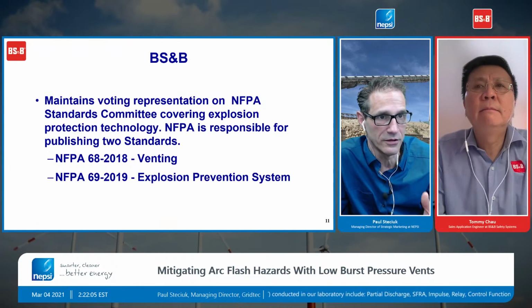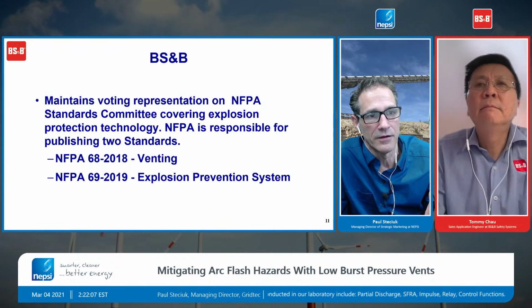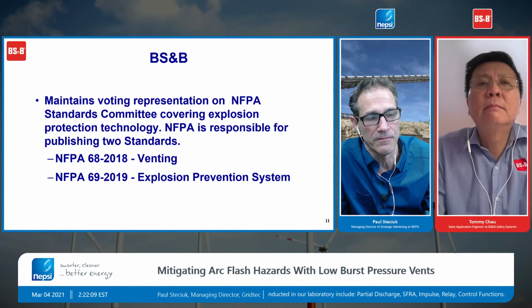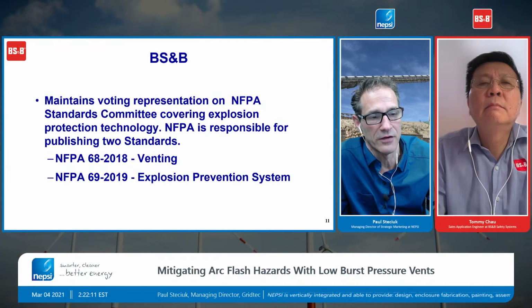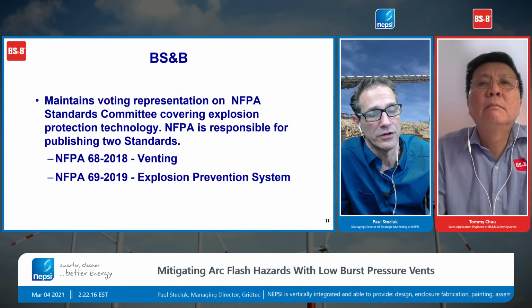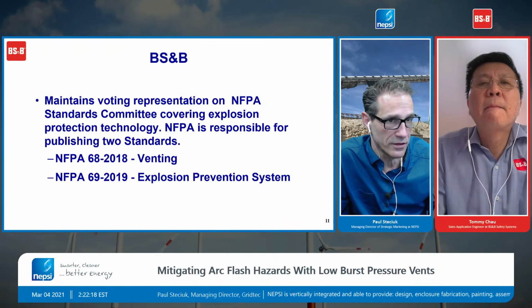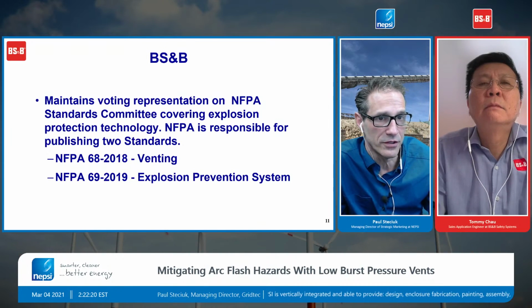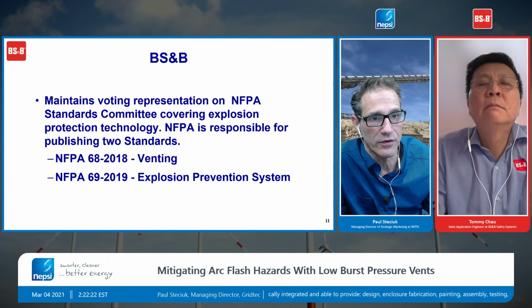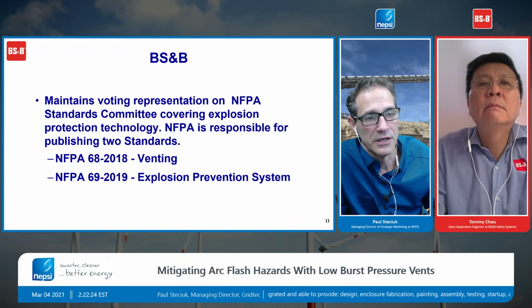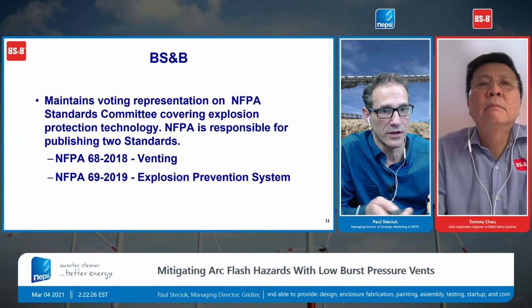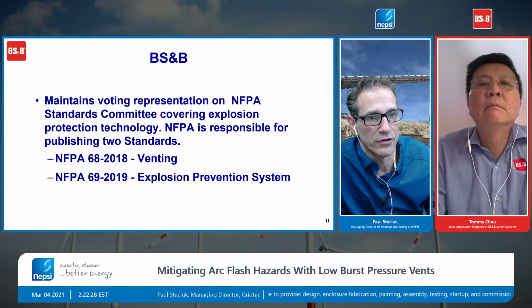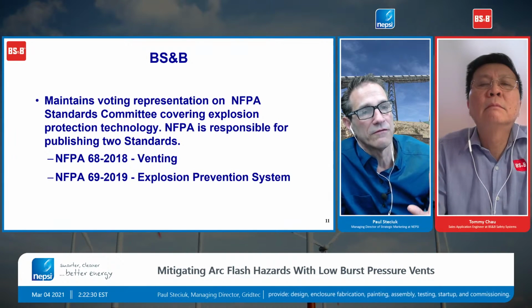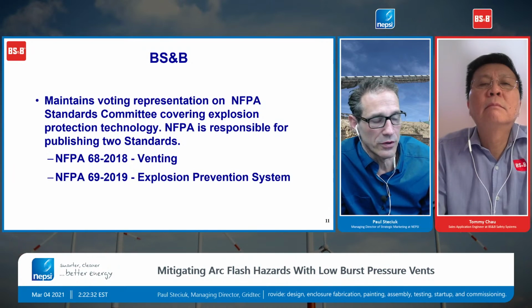It's a stainless steel membrane. It's got a certified release pressure. We put it on the back side of our enclosure, and we know that when the pressure gets up, in this case, I think 0.5 is what these are rated for, 0.5 pounds per square inch. And we can calculate those forces on the walls of our enclosure, what kind of forces we're going to have. We know that the vents are open.